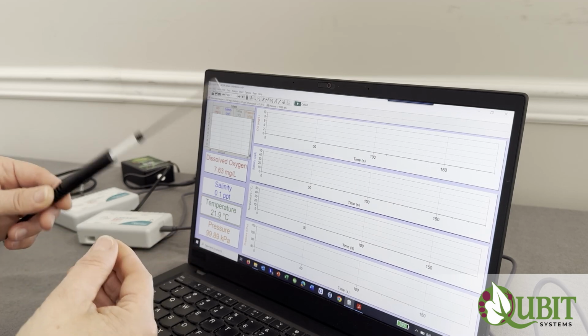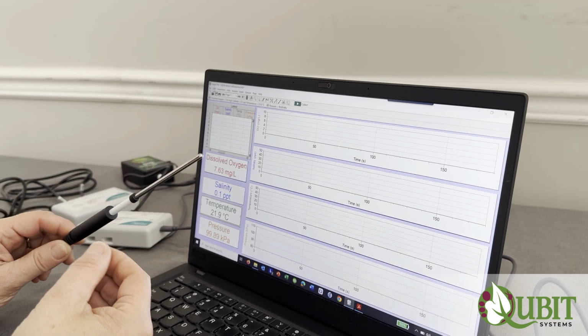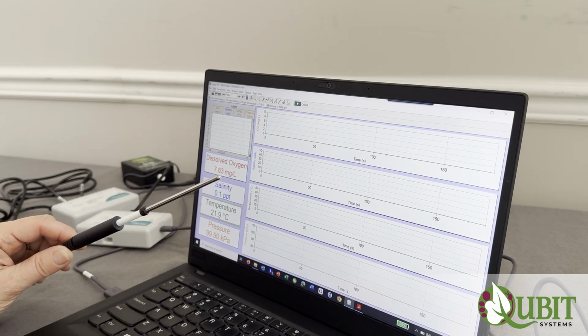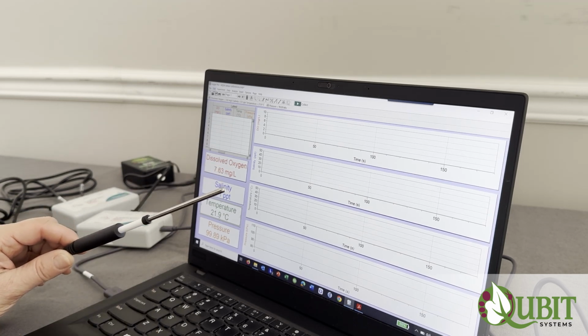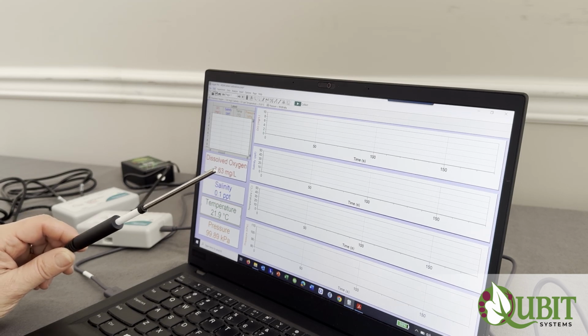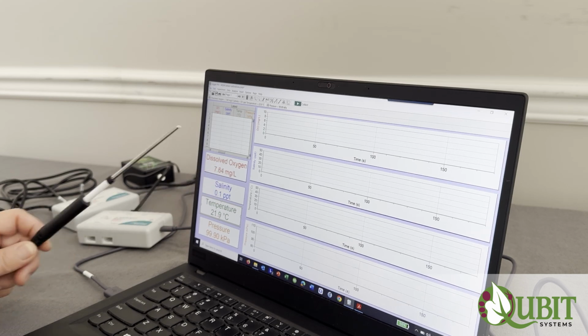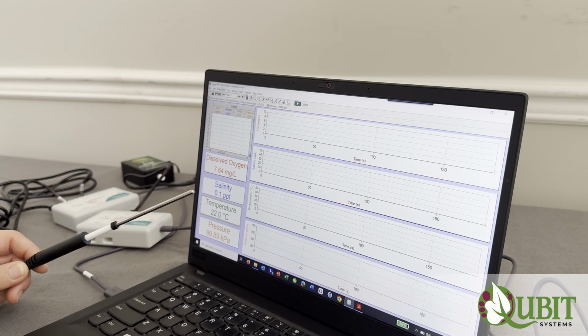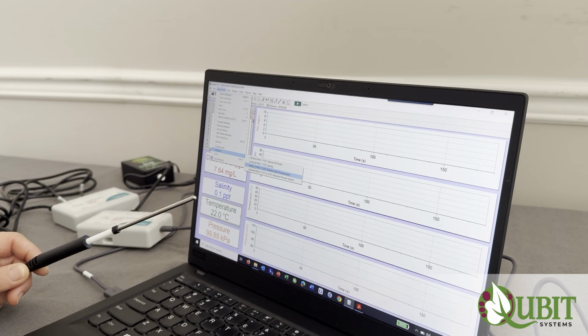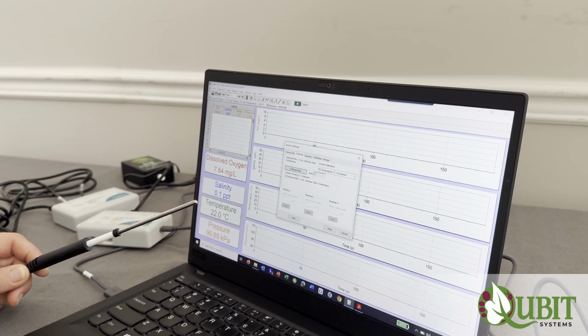The temperature probe that's provided with the package maintains its calibration very well. So there is rarely need to calibrate the temperature probe, but if for some reason that was required, the procedure is very similar to what we've already described. One goes to experiment, calibrate, select the stainless steel temperature probe.